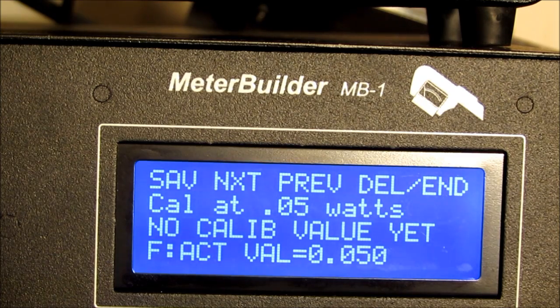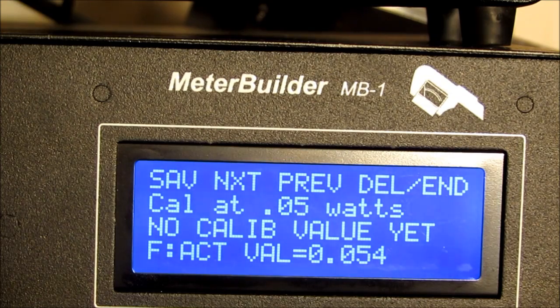We'll try to calibrate, and one of the difficulties you're going to find is dialing in the exact value of the calibration. What you see here is available by making use of the front panel pot. You can't see me turning that, but I'm turning the front panel pot up or down. And the nominal value is 0.05, but if the closest value I can set my transmitter to, as determined by the reference meter, for example, is 0.048 or 0.045, I'll dial that number in here before I go ahead and hit the save button to save that calibration.